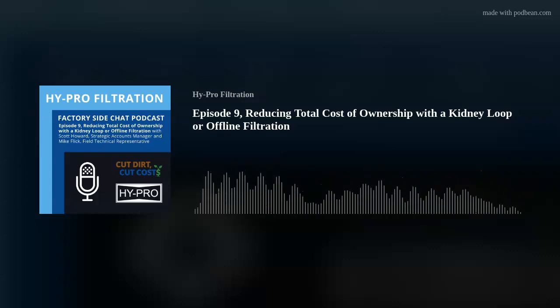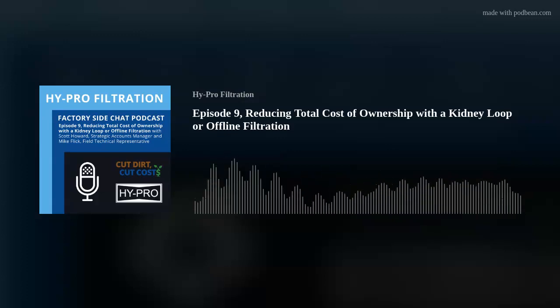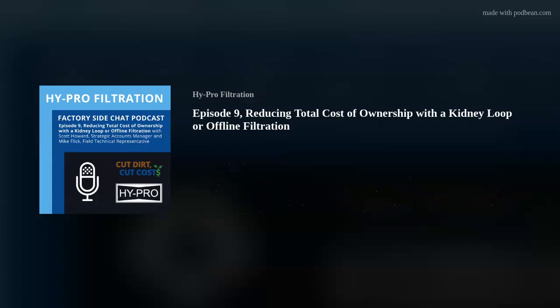And instead of using a very expensive high pressure filter or a large return filter, kidney loop filters are usually smaller and less expensive than the other two. So not only are you consuming a less expensive filter, but also by having the oil being cleaner, your hydraulic components last longer, your bearings last longer, your maintenance people have to do less emergency downtime repair, and they can focus on more preventative maintenance and forward-looking maintenance, and start actually doing the preventive maintenance instead of reacting.